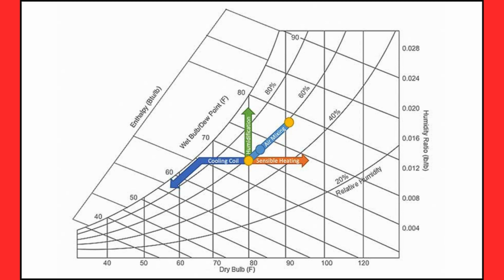on it. Key concepts in HVAC psychrometrics include dry bulb temperature, DBT, the temperature of air measured with a regular thermometer. It indicates the average kinetic energy of air molecules. Wet bulb temperature, WBT, the temperature to which air can be cooled by free evaporation of water into it. It measures the ability of air to absorb moisture.